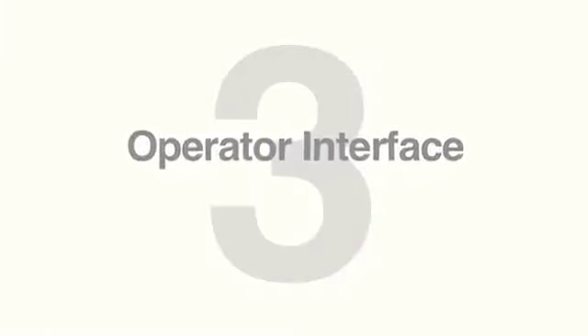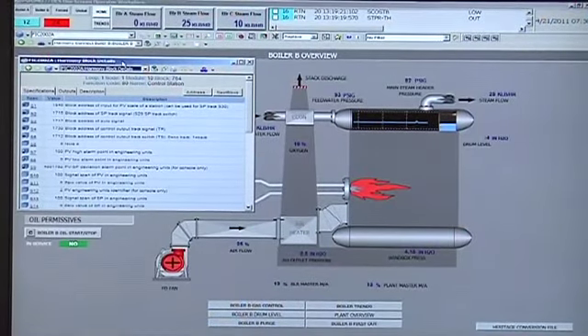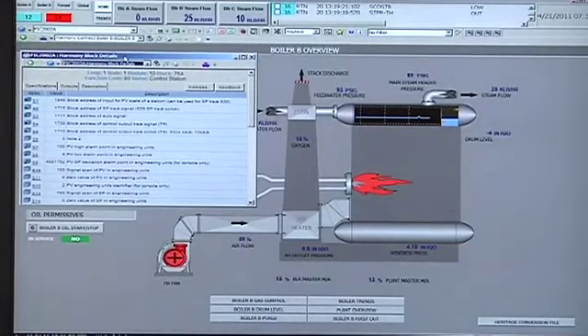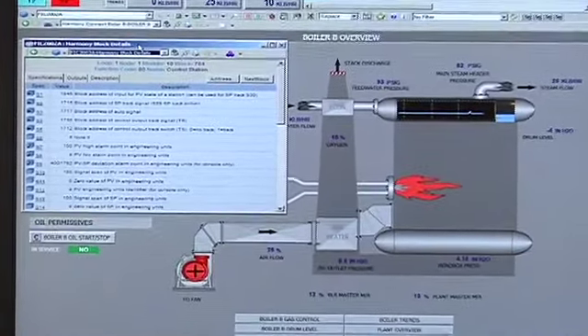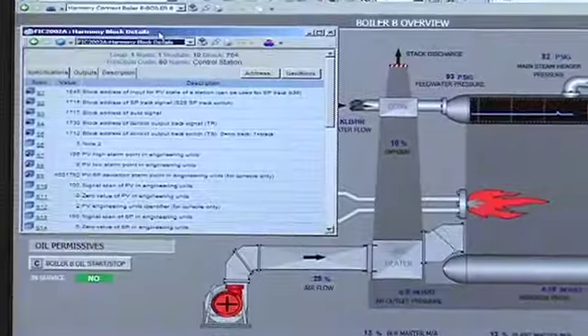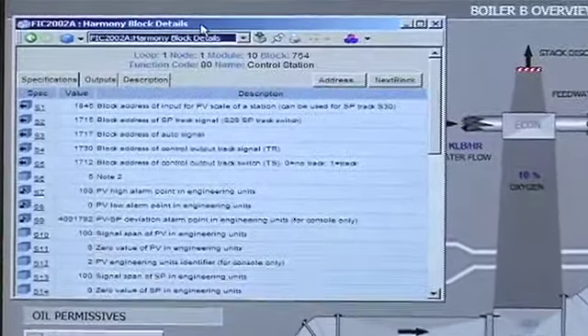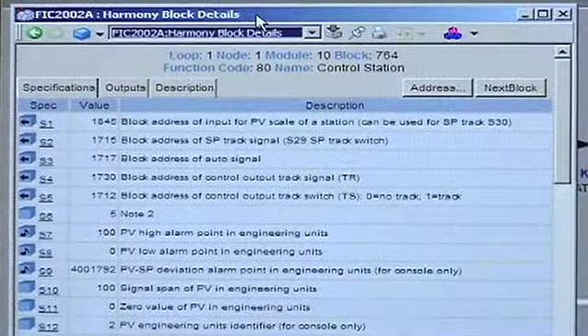The third thing you might want to consider is the operator interface. Some of the things to look at are, first, the operator graphics — you'll want to make sure those are converted so as to minimize any impact to operations. Second, you want to make sure that the operator interface contains the same level of system diagnostics and maintenance displays that you've always had within your control system.